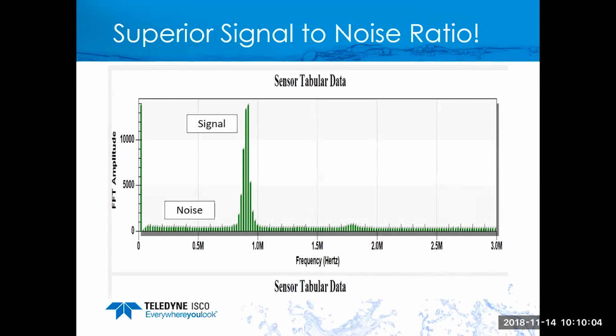What that means to you is that the laser will read extremely slow velocity as well as very clean water. With the first generation laser, we had a lot of noise at the low end, so our minimum velocity was 0.8 feet per second. We can now read much, much slower velocity than that.